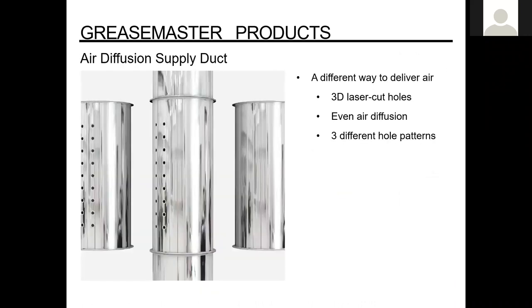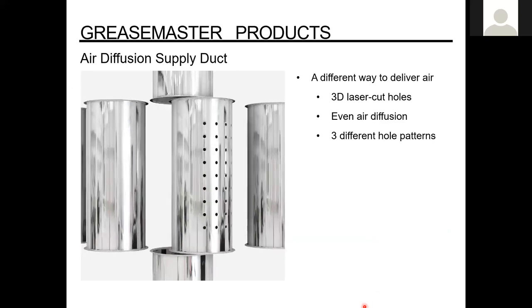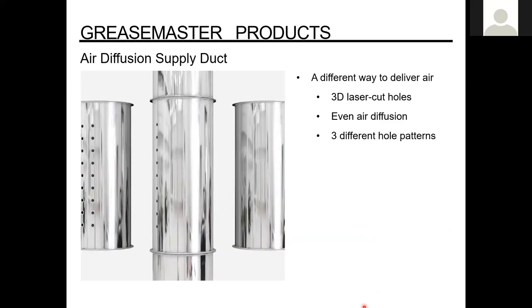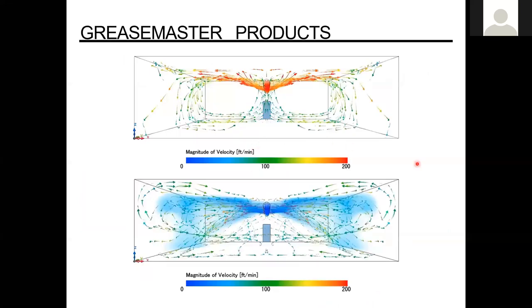Another newer product that we're getting into now, we saw that on the one diagram, is the air diffusion supply duct. It's definitely something new in the US, you don't see too much of this kind of stainless diffusion duct. Utilizing 3D laser cut holes, it's providing an even air diffusion. And there are three different hole patterns. Showing you a couple of the different ones here. We also did some of the CFD analysis on this. The top one shows how the heating is provided when the warm air is supplied through the duct, quickly dispersing and mixing through the conditioned space.